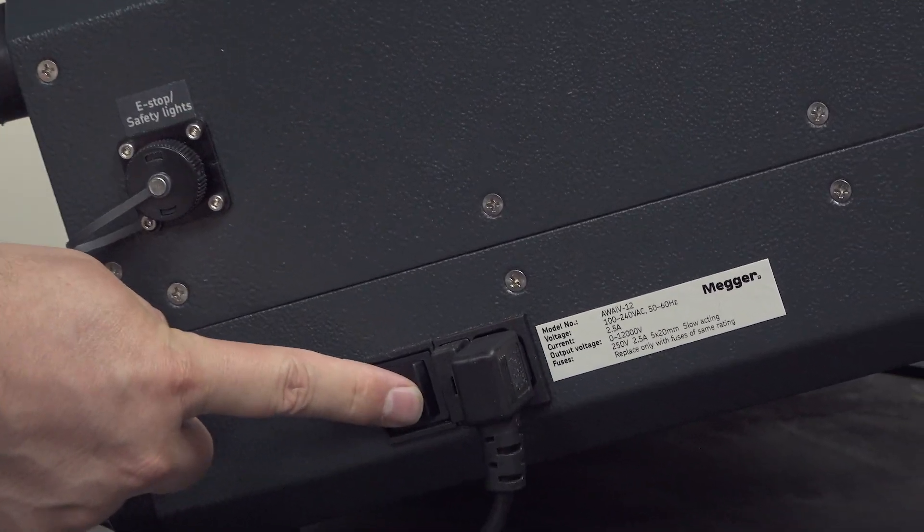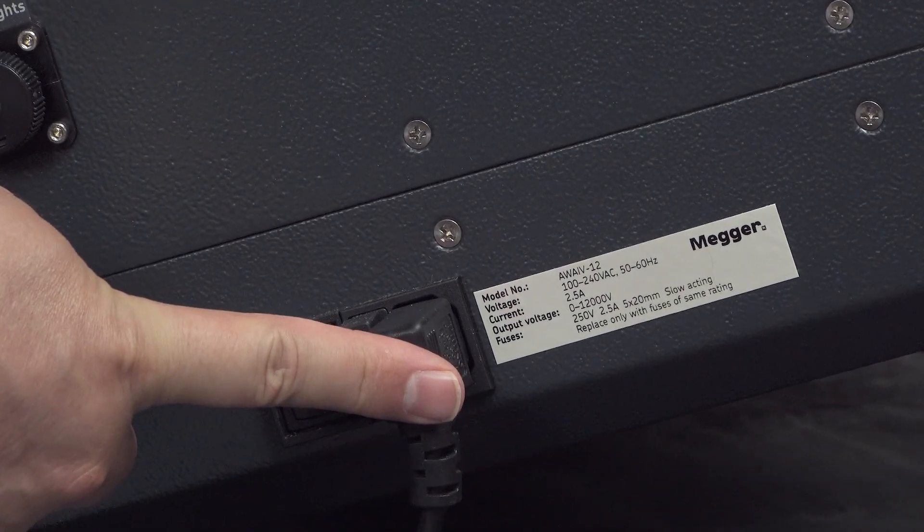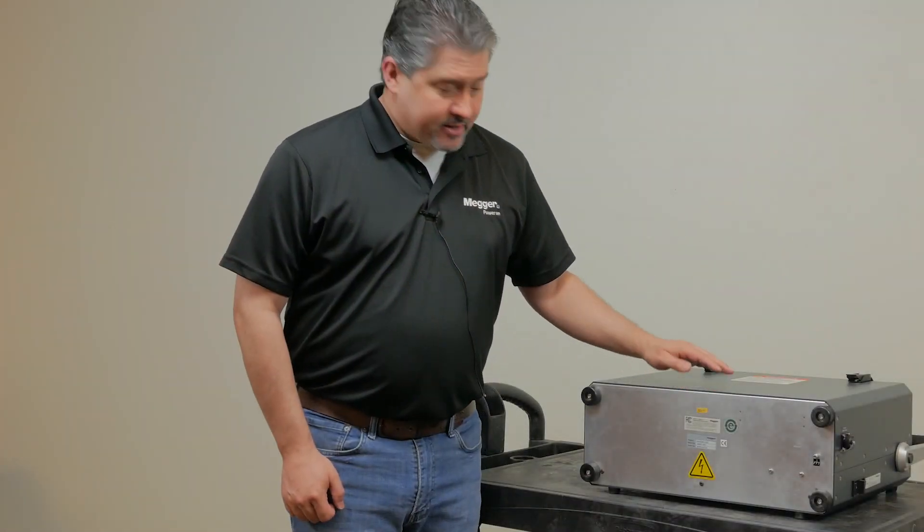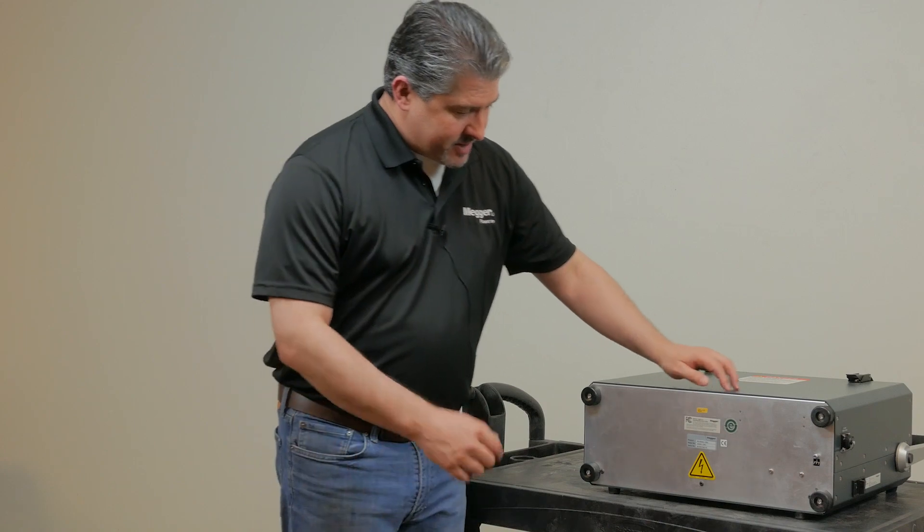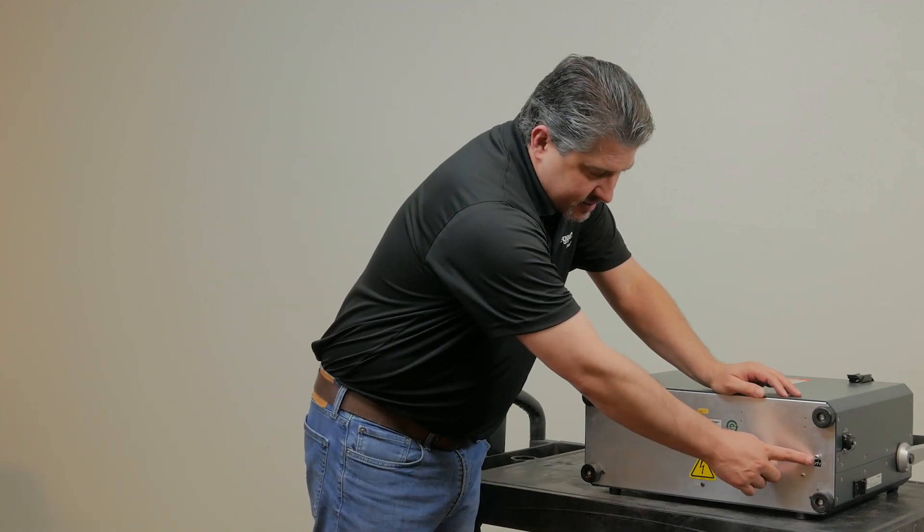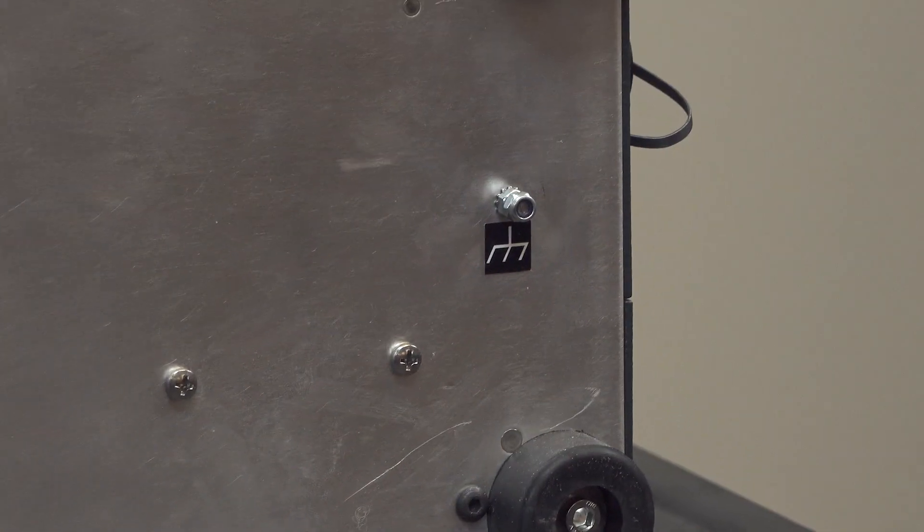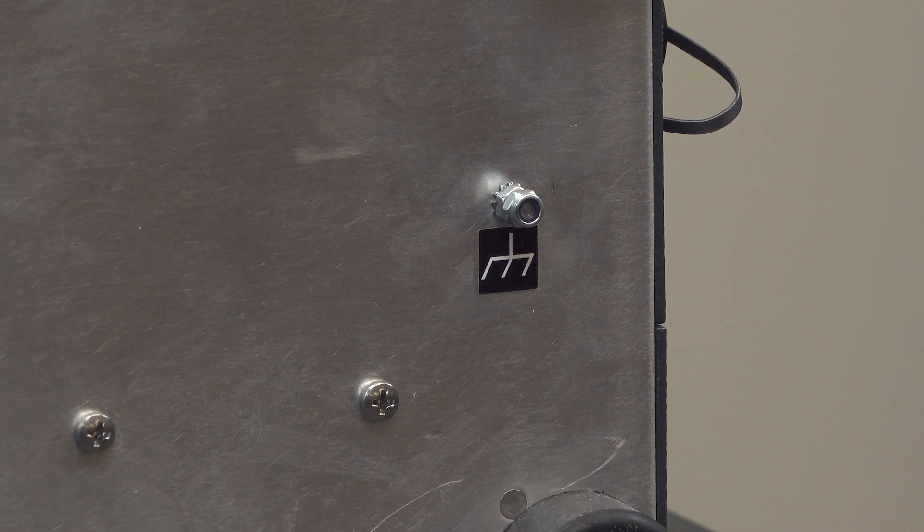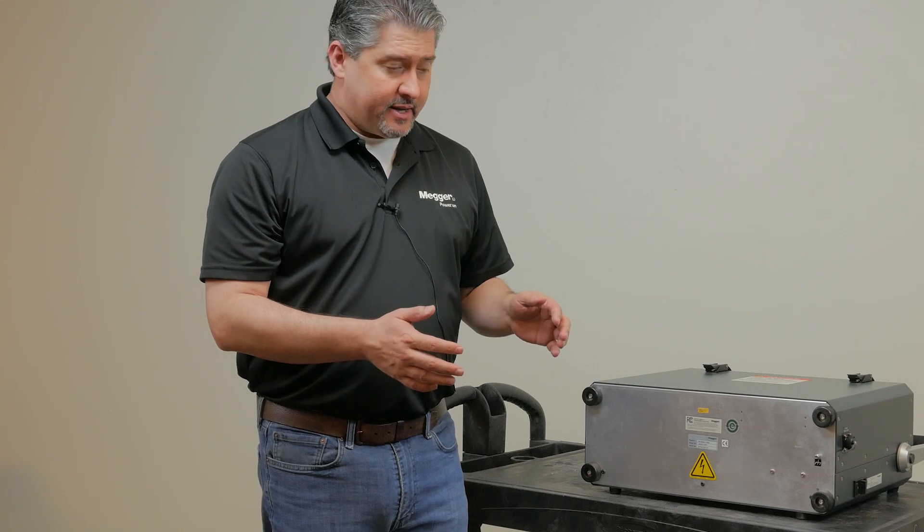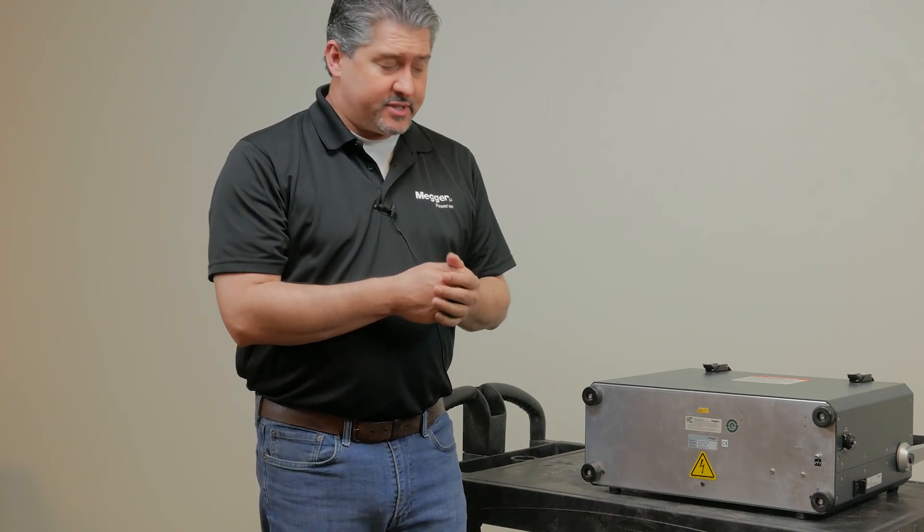Of course we have the on-off button and the power supply cable. The back of the AWA has a few things we'd like to point out. The first is the ground post that's provided to ground the chassis external from the power supply. You'll want to use that if you're in an ungrounded distribution system.